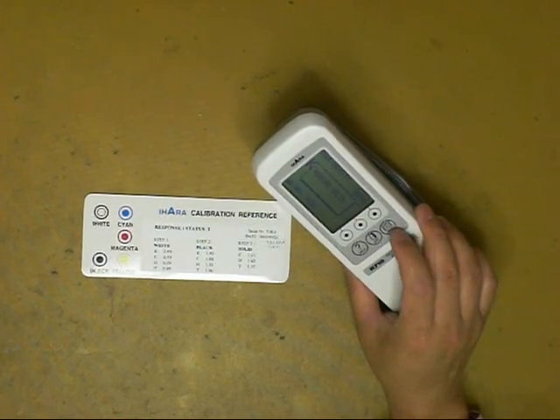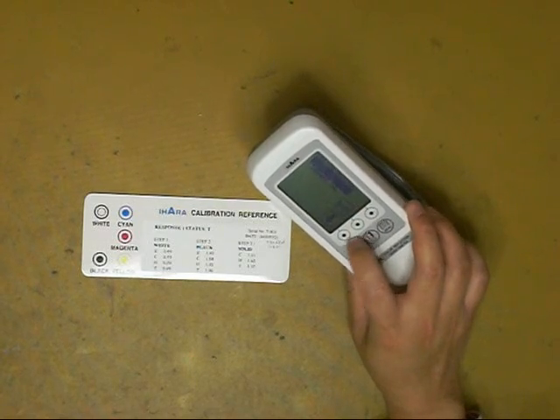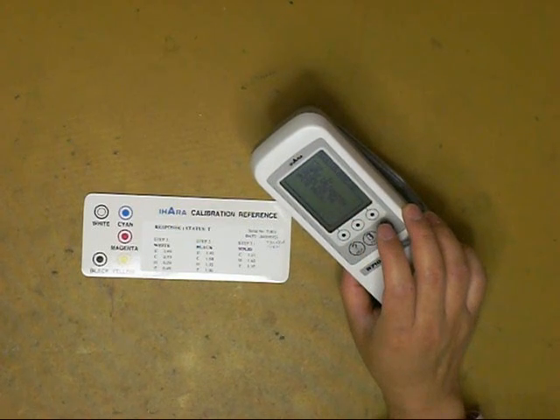Once the instrument is on, press menu, select calibration, and hit enter. Move to standard calibration and hit enter to begin step one.